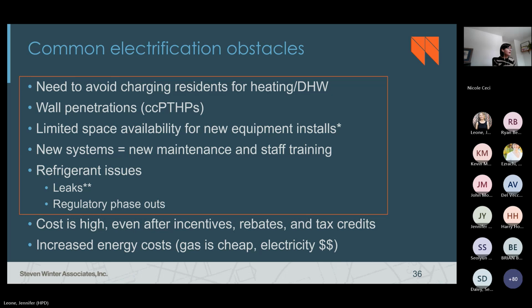Regulatory phase-outs are definitely easier to deal with when your refrigerant is in packaged equipment. At end of useful life, you replace that packaged equipment — you can swap in new generations of air-to-water heat pumps, terminal units, water-to-water heat pumps, etc., all while maintaining the same distribution system. So those are the items in the orange box, where an electrified hydronic approach gives you some wins. The other items on this list, we're not fixing.